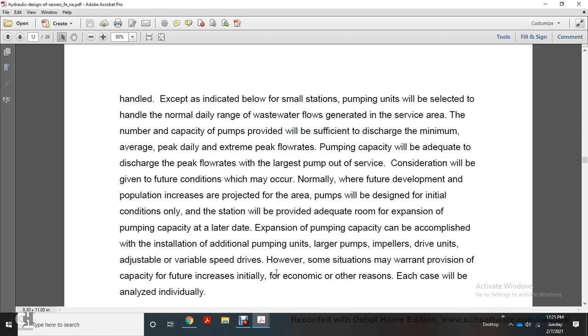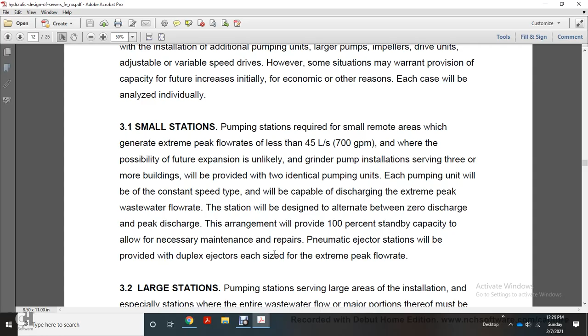Small stations. Pumping stations that serve small remote areas generating extreme peak flow rates of less than 700 gallons per minute, where the possibility of future expansion is unlikely, and grinder pump installations serving three or more buildings, will be provided with two identical pumping units. Each pumping unit will be constant speed type and capable of discharging the extreme peak wastewater flow rate. The station will be designed to alternate between the units. The arrangement will provide 100% standby capacity to allow for necessary maintenance and repairs. Pneumatic air ejector stations will be provided with duplex ejectors, each sized for the extreme peak flow rate.